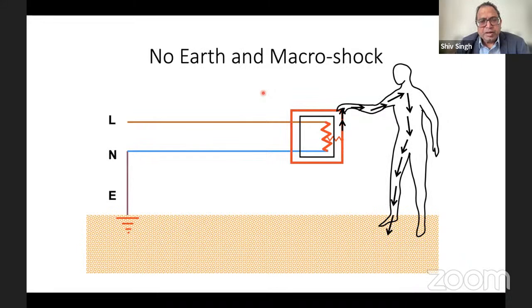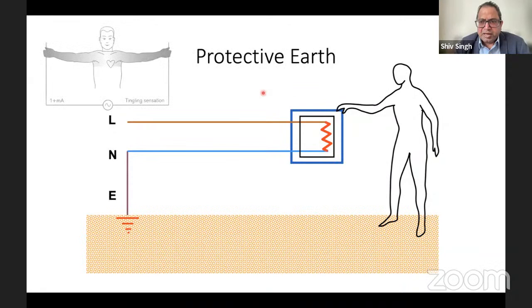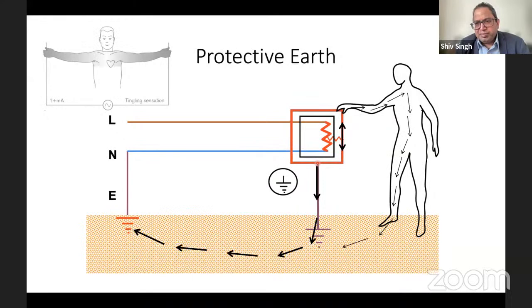But if the body is earthed, with the earth connected to the body of the equipment, this is called protective earth, and it is a path of least resistance. So when there is a leakage of current, most of the current will pass to the earth. If you touch it, a very small current passes through you, even less than 5 milliamps or 1 milliamp. You may feel a tingling sensation, or not feel anything at all. So the protective earth is important for us, and it protects us. All the equipment and gadgets at home have protective earth because macro shock should not occur at home. But when this earth becomes disconnected and there is a leakage of current because of wear and tear, wires becoming loose or coming off, that causes danger. So earth is protecting us. The protective earth is important for preventing macro shock.